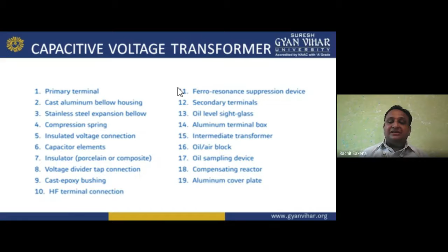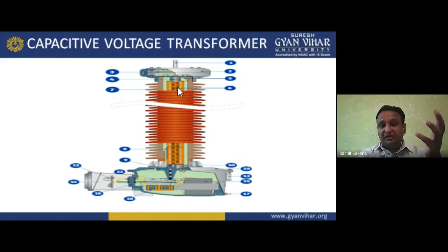Twelve is the secondary terminals. Thirteen is the oil level sight glass, which we can find here. Fourteenth is the aluminum terminal box. Fifteen is the intermediate transformer. Sixteen is the oil oblique air block. Seventeen is the oil sampling device. Eighteen is the compensating reactor, for compensation purposes, and nineteen is the aluminum cover plate. So these are all the 19 parts of the capacitive voltage transformer. I hope you understand. Now moving forward.